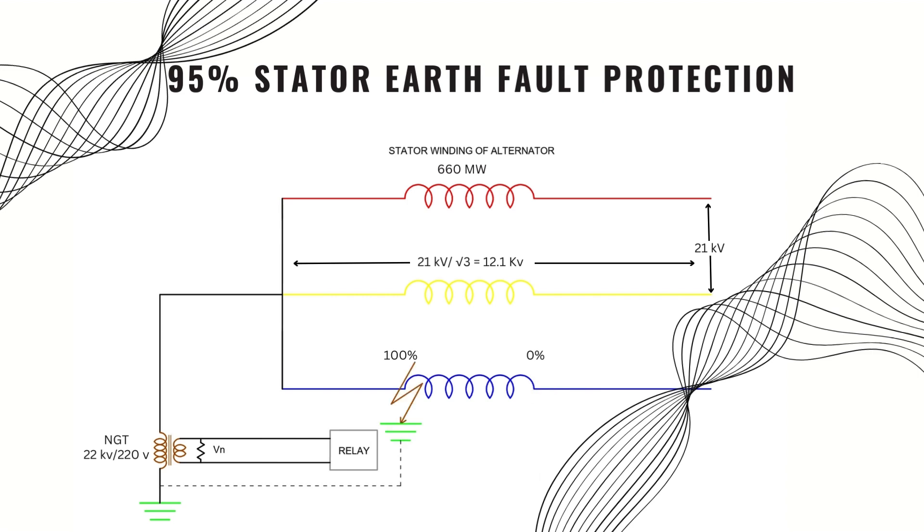But what will happen if any fault occurs near the neutral terminal which is outside of the 95% portion? In this context, this protection scheme will not work because if any faults happen near the neutral terminal, the voltage across that portion is very low. For example, 100 volts, then VN will be 1 volt which is much less than the predetermined value. So relay will not sense any earth fault.